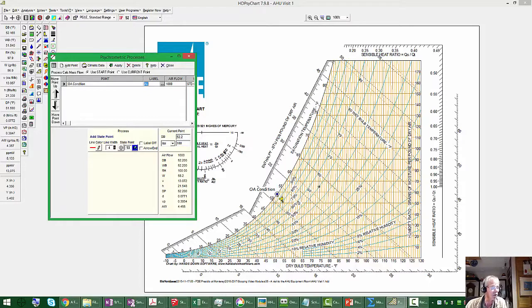And it's probably a little higher, because there are other things in the building that add moisture, like people, for instance, and cooking processes. But if we just made a simplifying assumption and said, well, we're going to assume the specific humidity in the building, the pounds of moisture per pound of dry air, or grains of moisture per pound of dry air. We can talk about what grains means and why we'd use that, but it goes back to the slide rule days. We're going to assume that's the same as it is outside.